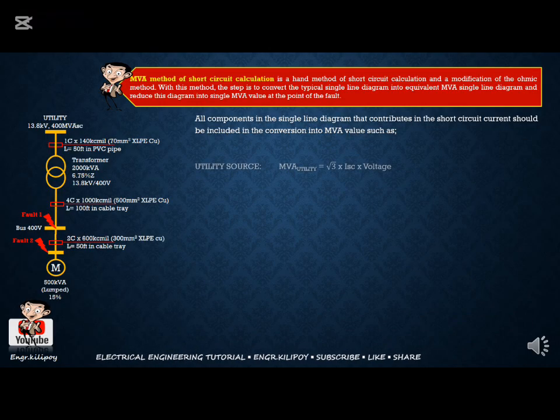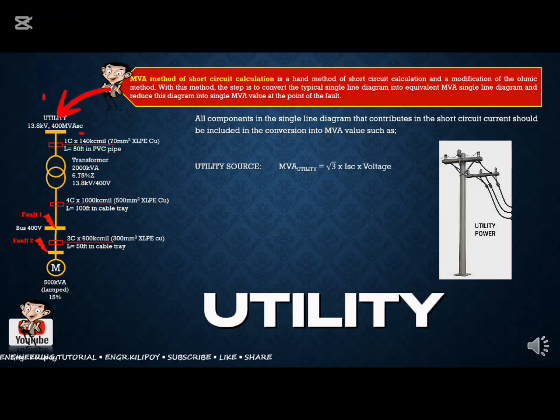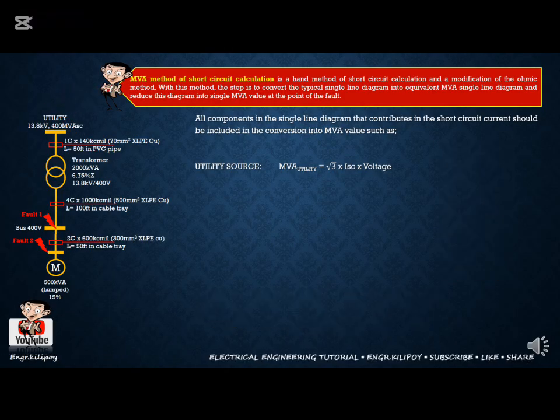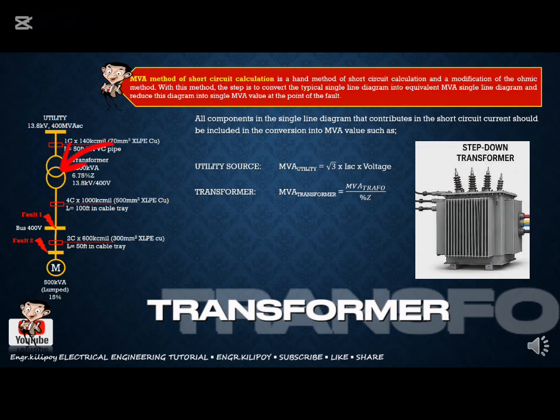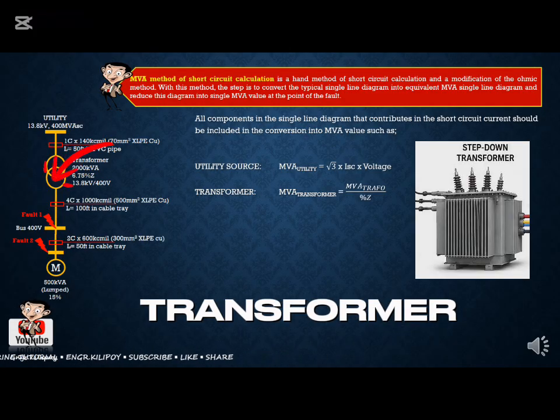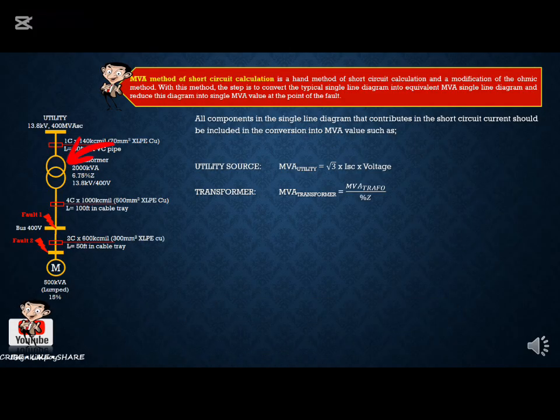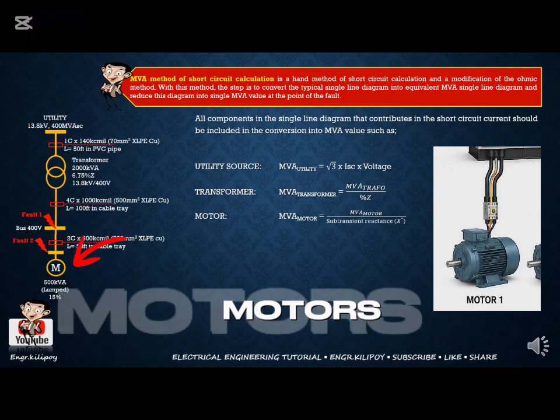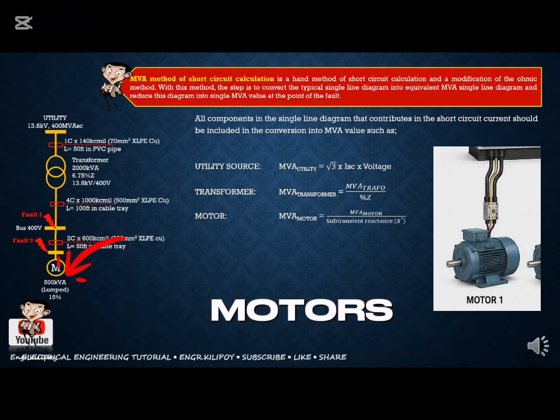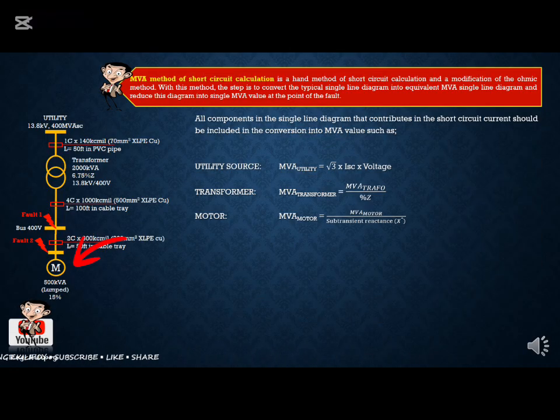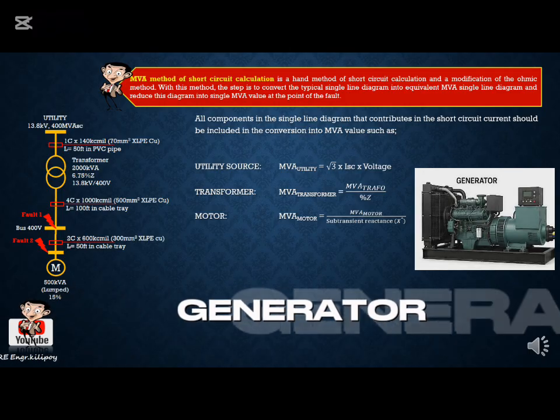For example, the utility. So this is the formula of converting the details to the MVA equivalent of the utility. For the transformer, MVA of the transformer divided by the impedance voltage or yung percentile niya. And yung motor, if your electrical system consists of electric motor load, kasama yan sa kailangan mo i-convert as MVA. It is calculated as MVA of the motor over the subtransient reactance.